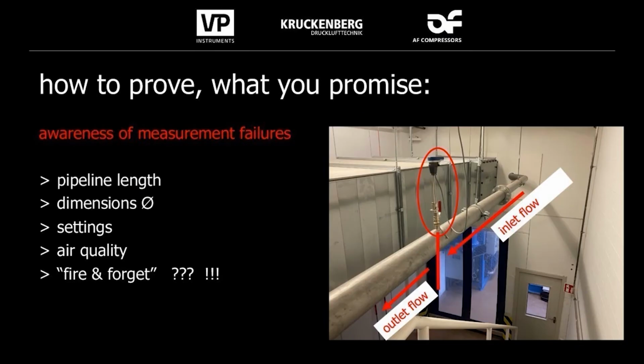And a very important point I want to indicate is that you have to be aware of measurement failures. In the beginning, the client provided us with measurement data. They tried it by themselves. Energy measurements, amp meters were installed wrong. We were facing, for example, a 55 kilowatt oil lubricated compressor, which was only consuming around about 35 kilowatt, so 10 kilowatt less than expected. But normally the real energy consumption should be above 55 kilowatt for such a machine.